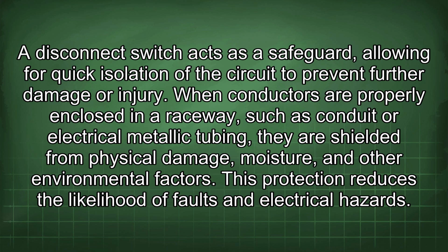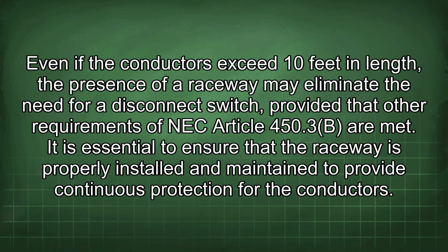When conductors are properly enclosed in a raceway, such as conduit or electrical metallic tubing, they are shielded from physical damage, moisture, and other environmental factors. This protection reduces the likelihood of faults and electrical hazards. Even if the conductors exceed 10 feet in length, the presence of a raceway may eliminate the need for a disconnect switch, provided that other requirements of NEC Article 450.3(B) are met.